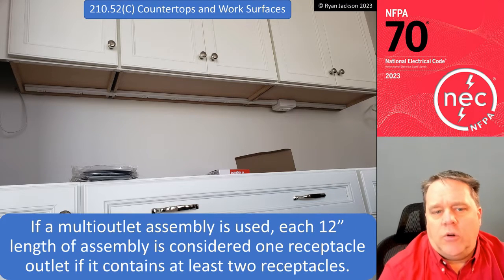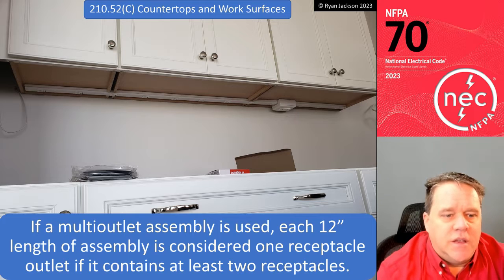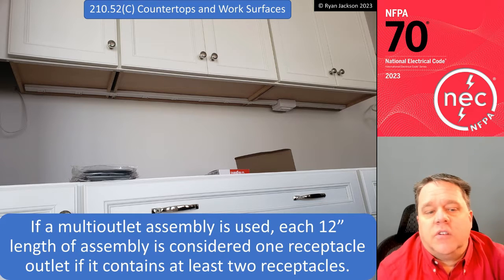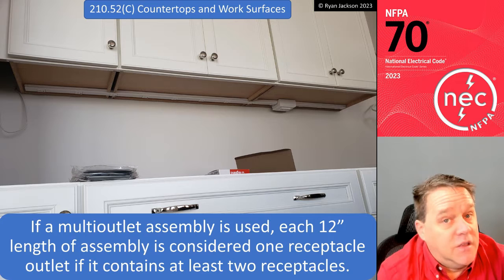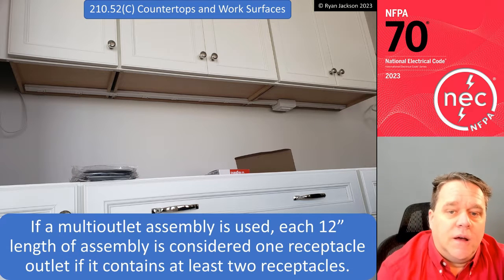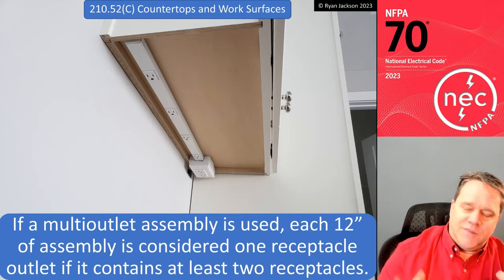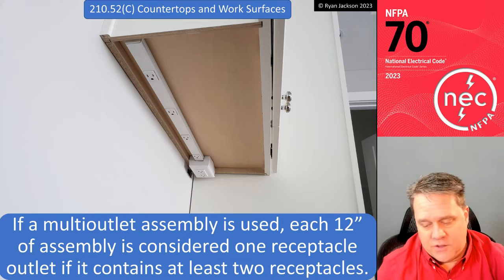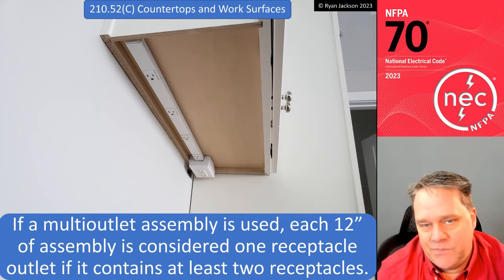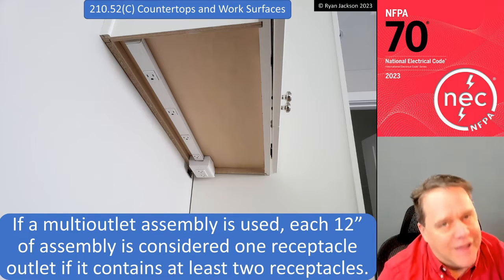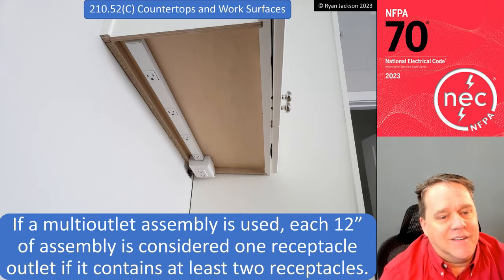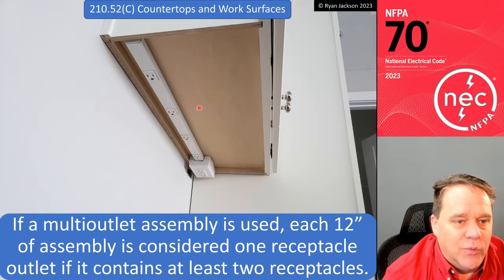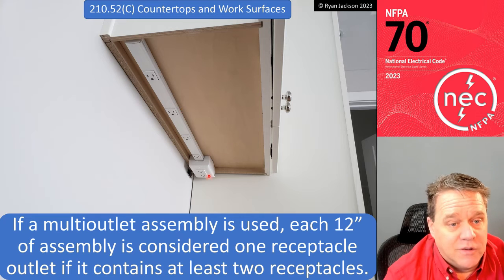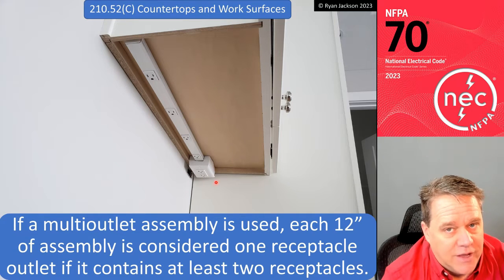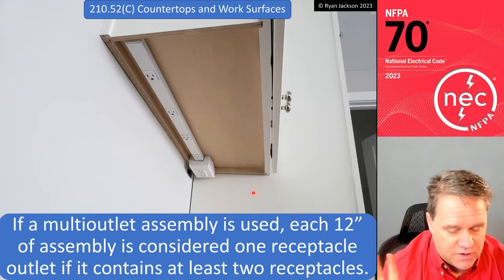If a multi-outlet assembly is used, then each 12-inch length of assembly is considered one receptacle outlet if it contains at least 2 receptacles. All right, so this is kind of a tricky one. The code doesn't tell you where you need receptacles. The code tells you where you need receptacle outlets, all right? And here in the photograph, we have lots of receptacles, but only one receptacle outlet. And I know that's dumb, but it doesn't matter.